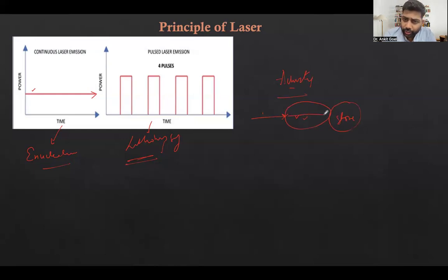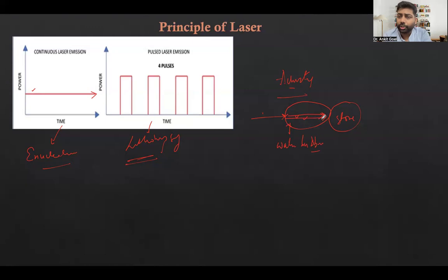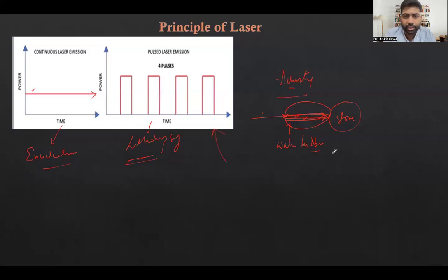How does the laser energy actually lead to stone fragmentation? The surrounding water gets heated by the laser energy and forms a water vapor bubble. This bubble creates a path for the energy to be transmitted to the stone — it doesn't travel directly itself. However, in doing so, there is some loss or dissipation of energy by the time it reaches the stone. That is the problem with single pulsed lasers — at every pulse, some effective energy is wasted in water bubble formation and path creation.